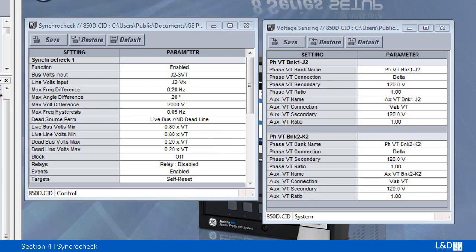Once permit is set and all conditions are met, then sync dead source ok operand will be sent to the transfer scheme. If magnitude, phase, and frequency differences are all below the settings, then sync one close permit operand will be asserted.